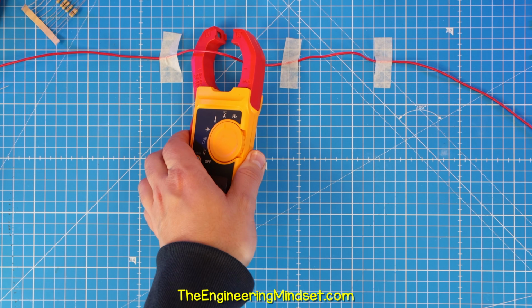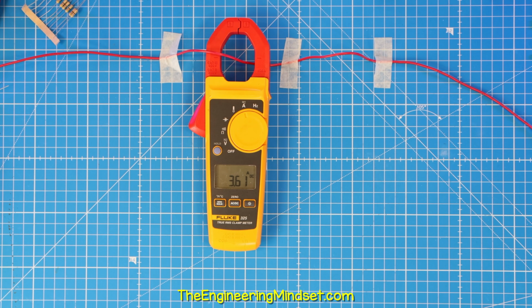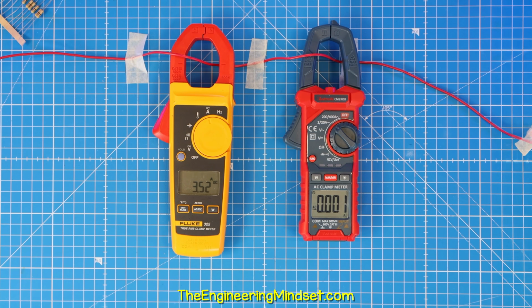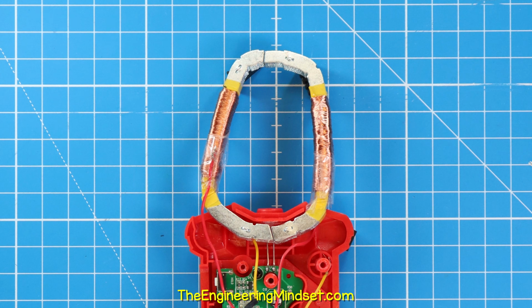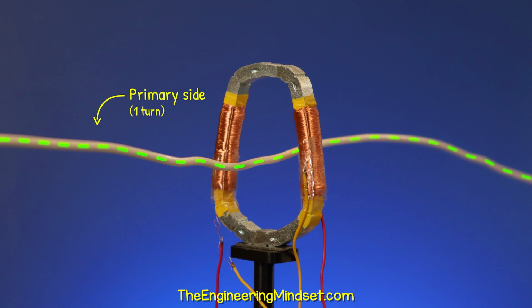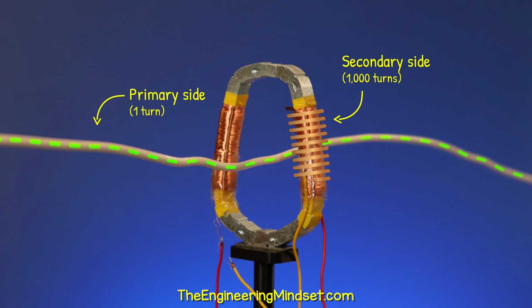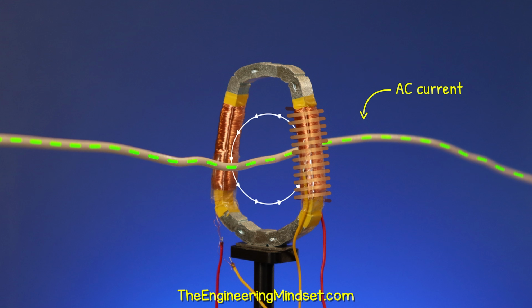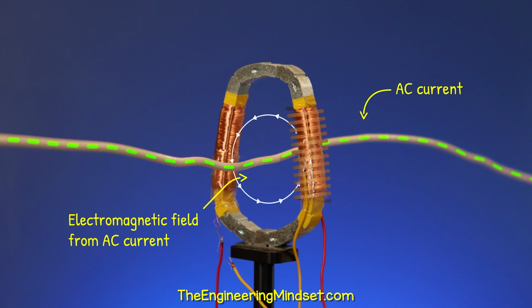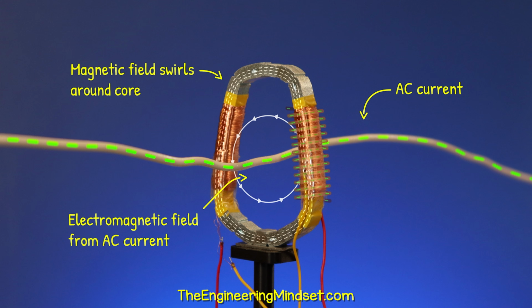Notice that this clamp meter shows around 3 amps of DC current, but this meter shows 0. That's because inside is a current transformer, which can only detect alternating current. The iron core is wrapped in a copper wire, which essentially just makes a secondary side of a transformer. The electromagnetic field of an AC current will be concentrated into the jaws of the clamp, causing a magnetic field to flow around the core.